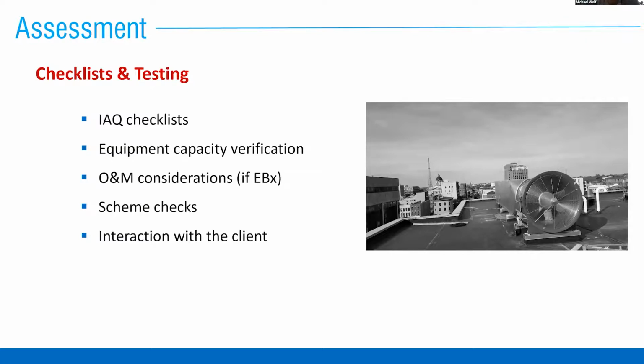But having them work on those, they can conduct scheme checks while on site. Where's the outdoor air coming into the air handling unit? What's the arrangement of the coils? Is there a static pressure switch or a static pressure sensor across the filters? What's that flexibility on site? Having that documented, you have boots on the ground.